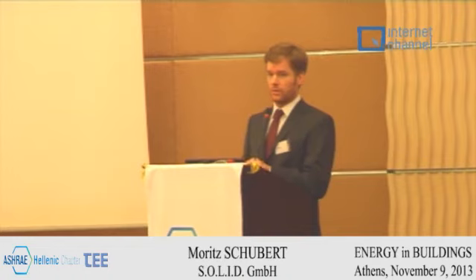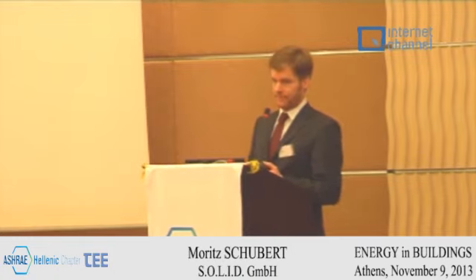Yes, we did. You can actually use it because if you have to cool down the cooling water for the cooling tower, let's say to 30 degrees, and you have a heat exchanger, you could heat up another water flow to around 25 degrees. So you could use this to preheat maybe domestic hot water, but for hygienic reasons and so on, normally you want to heat the domestic hot water to more than these 25 degrees, so you need another hot water system for that.